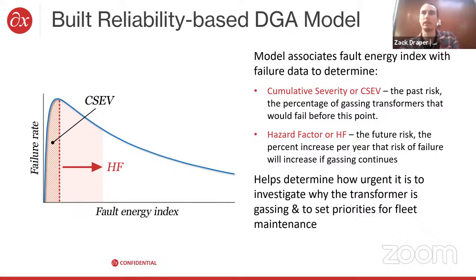Some of the things that we derived from that was a cumulative severity, which is an estimate of how lucky you got to where you're at today. So it's the fraction of transformers that would have failed had they had a similar level of gassing. And then we have the hazard factor, which is a forward projection in risk, where we look at the current gassing rate and the current failure rate in the model in order to determine what the risk is going into the next year. That can help you prioritize maintenance for things that are gassing in a very risky way versus transformers that are not gassing at all and appear to not have any risk of failure.